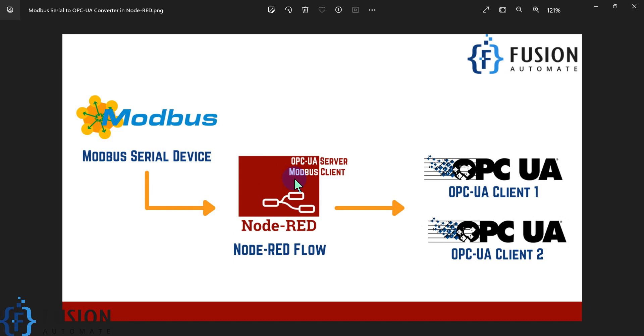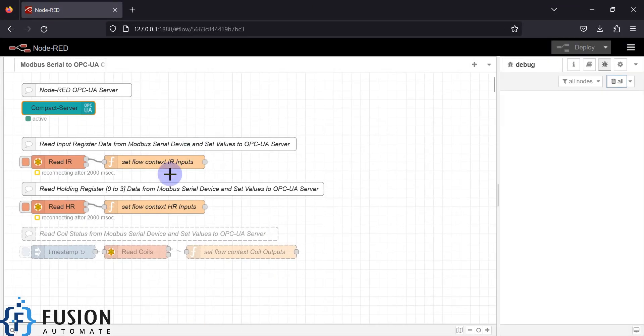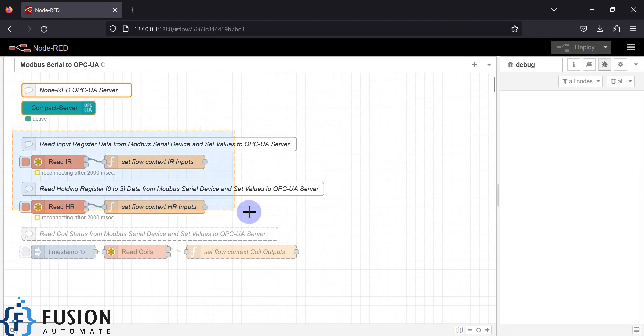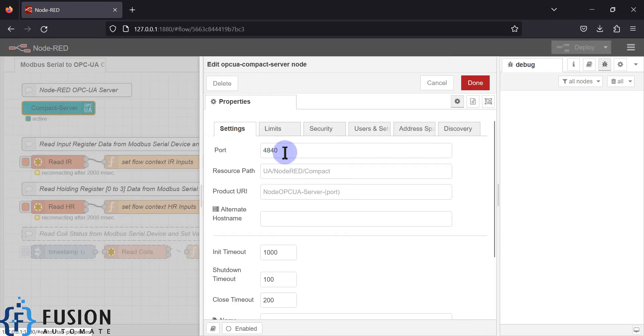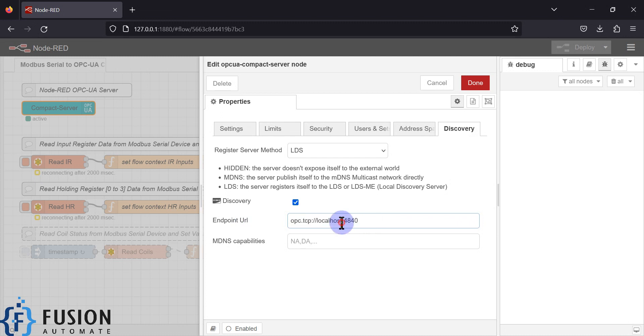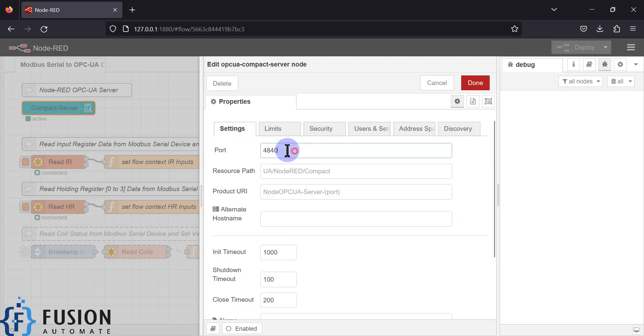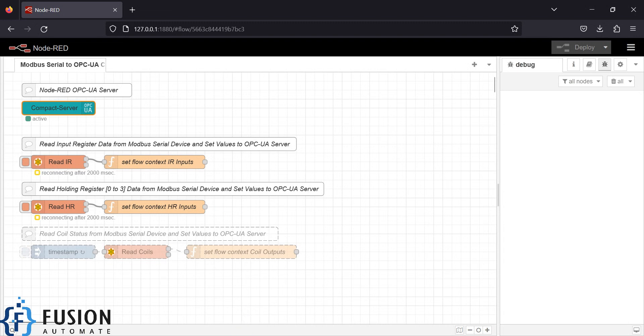We will see the demo to understand how this is possible. So here is my Node-RED flow. This node is to create the OPC UA server and this node is to read the data from my Modbus serial device and publish it to the OPC UA server. If you double-click here, you can see I have set the OPC UA server port to 4840 — you can set other ports as well. Here is my endpoint URL, which I can use to connect from my OPC UA client, or I can browse port 4840 to find the OPC UA server.